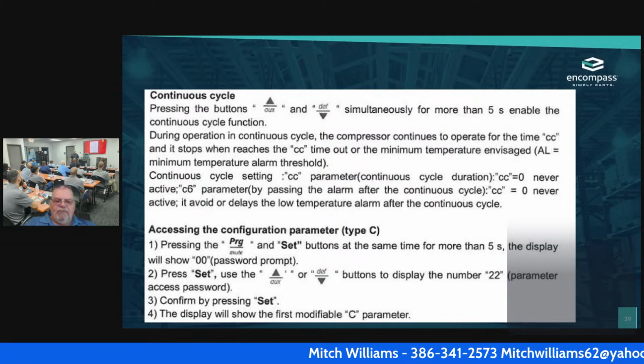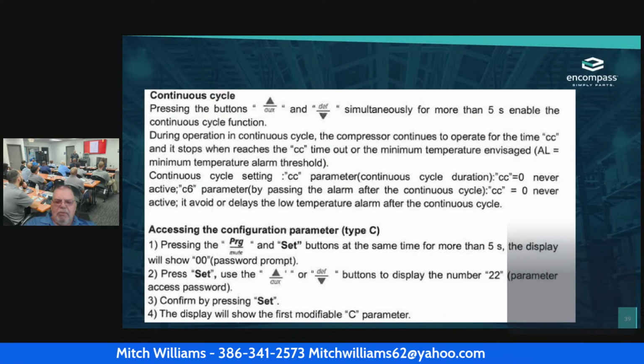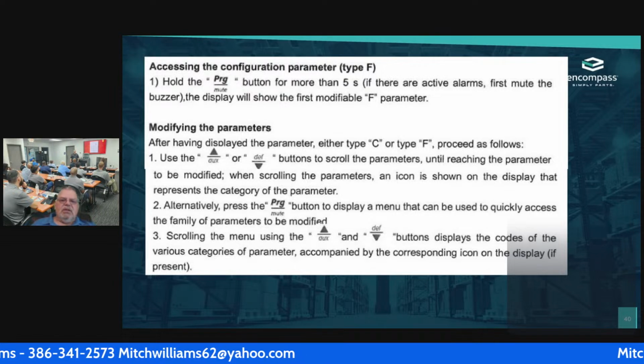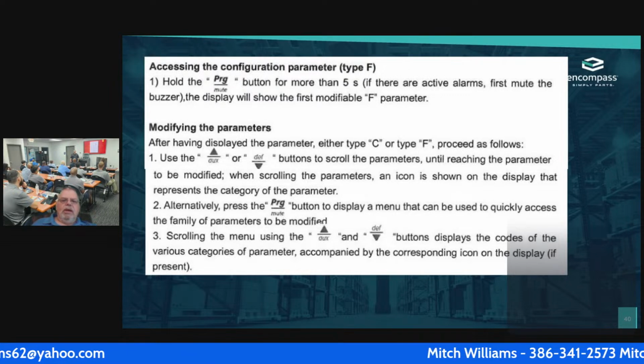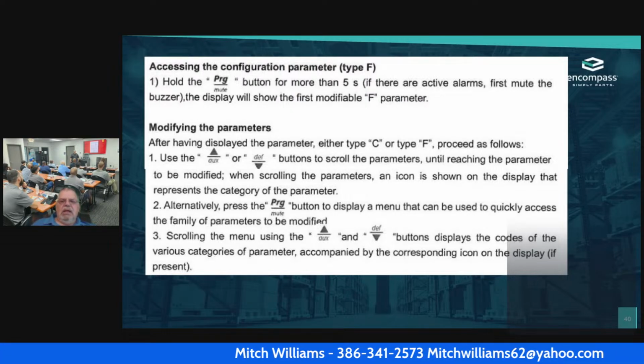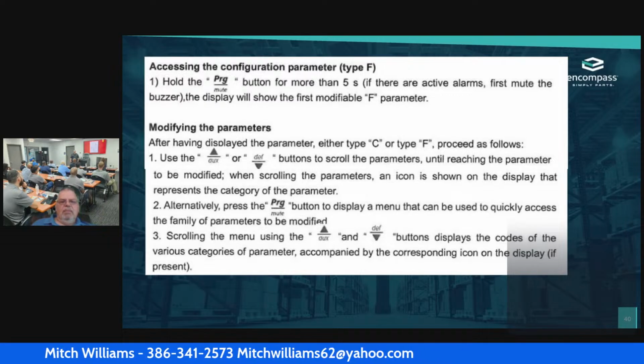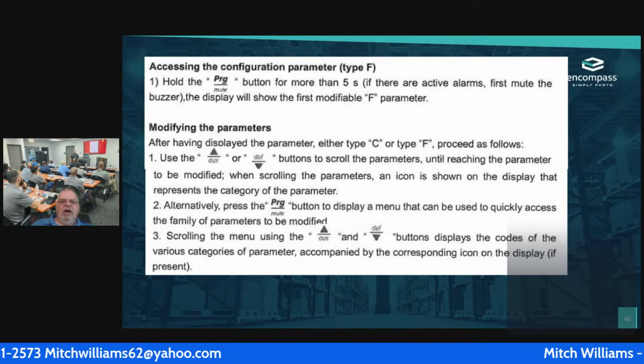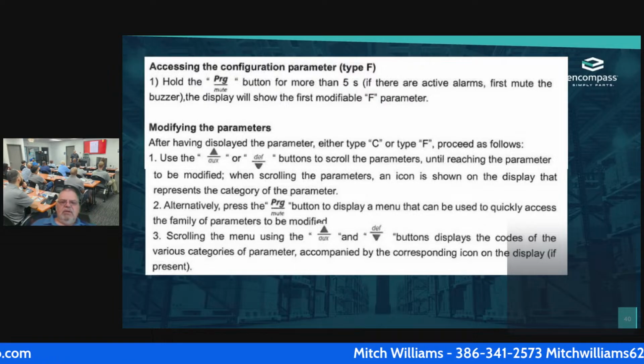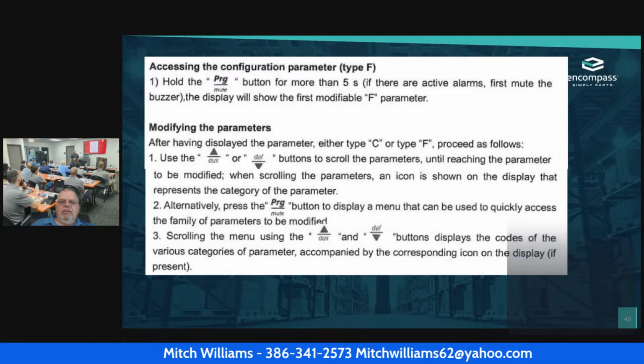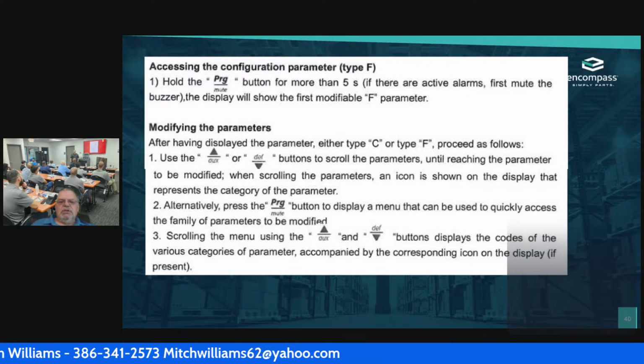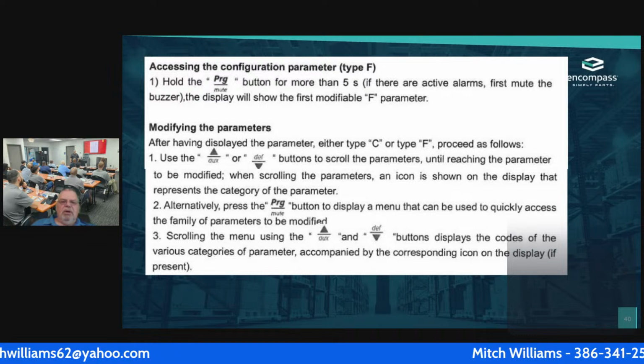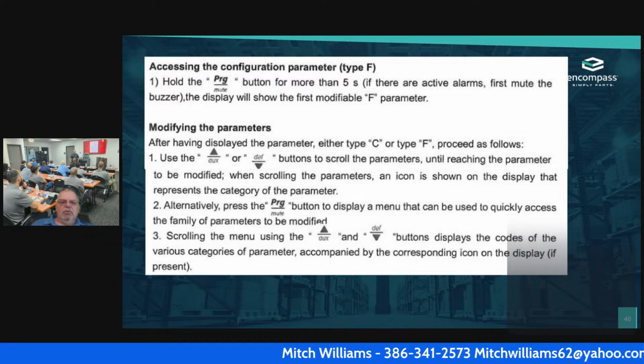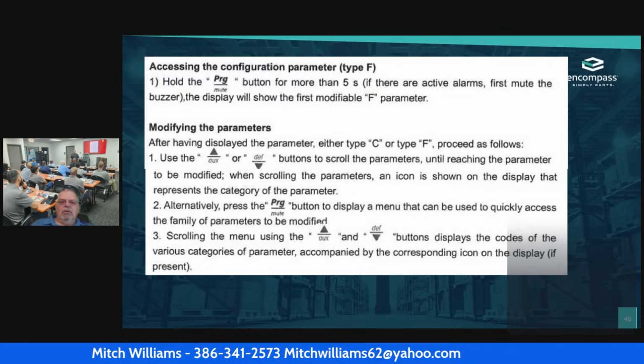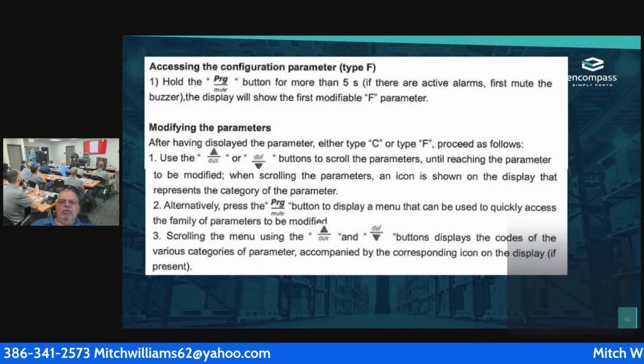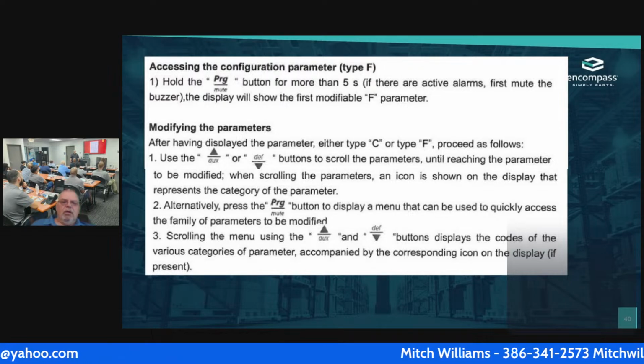The display will show the first modifiable parameter. Okay. Then I can access the configuration parameter. Hold the program button for more than 5 seconds. If there are any active alarms, first mute the buzzer. Then the display will show the first modifiable F parameter. After having the displayed parameter, either C or F, proceed to the following. Use the up button or the down button to scroll through the parameters until you reach the parameter that you want to modify. When scrolling the parameters, an icon will show on the display that represents the category of the parameter.